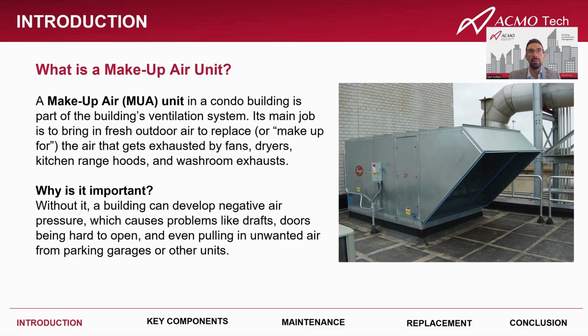So why are they important? Well, fresh air supply helps keep corridors comfortable. It helps odor migration between units to be managed. It reduces humidity buildup, which is extremely important for multi-residential condominiums. And most importantly, it keeps indoor air safe by making sure you're not breathing contaminated air from other spaces.